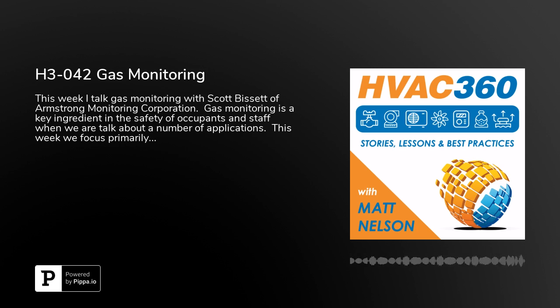And if you're not catching on to what I'm saying, say you have a refrigerant leak, which is a typical place we'd see this. If you had chiller equipment in a mechanical room and there was a refrigerant leak, you'd want gas monitoring there to be able to detect that leak so you can start an evacuation sequence. Or if you're in a parking garage or a loading dock area, and you have cars idling, or a lot of buildup of products of combustion, you want to be able to ventilate that properly. You want to be able to detect when the level goes too far to be able to activate that ventilation sequence.